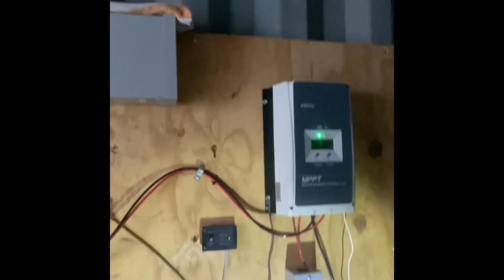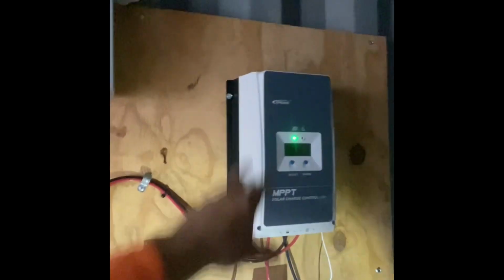So these circuit breakers control from the solar panels down into my charge controller. At any moment when I want to power off these devices, all I got to do is flick these circuit breakers to stop the incoming solar charge. You definitely want to put a circuit breaker after each main electrical device. So I have solar panels, circuit breaker, charge controller, circuit breaker, batteries, circuit breaker, inverter, circuit breaker.